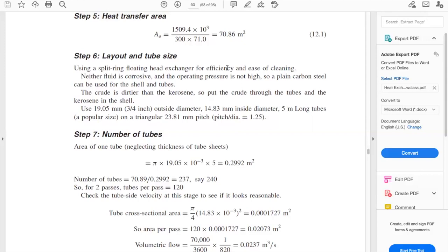Step six is to set up the layout and tube size. This will change from team to team because some of you will select different layouts. This problem selects a split ring floating head exchanger for efficiency and easy cleaning, because a fixed tube sheet layout creates problems cleaning outside the tubes and doesn't allow free thermal expansion of the material.